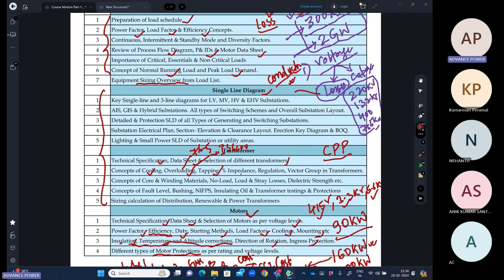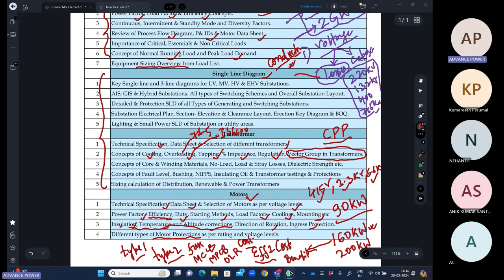Tapping impedance, it's a very useful parameter for transformer. Transformer regulation, vector group in transformer. So it's a very important topic. I will discuss in a very easy way. You will never be able to forget this vector group. Then we'll discuss about the core winding material, all the losses. So in this losses, again, we'll discuss about the loss capitalization as per the CEA methods also.